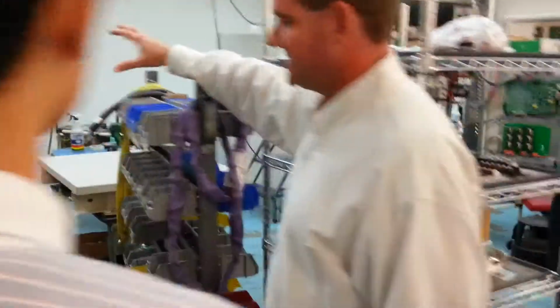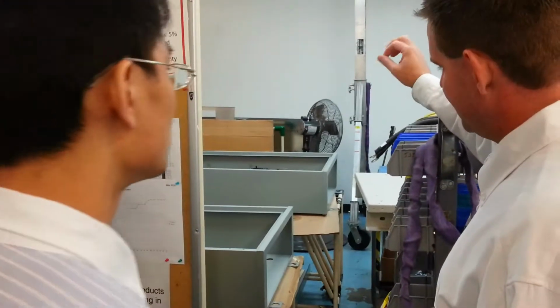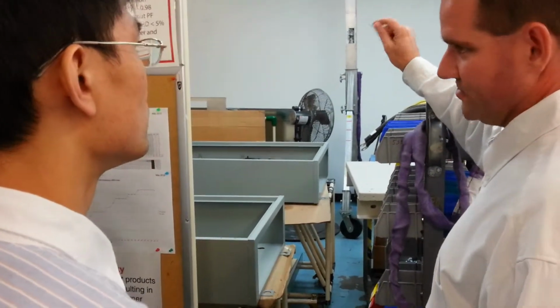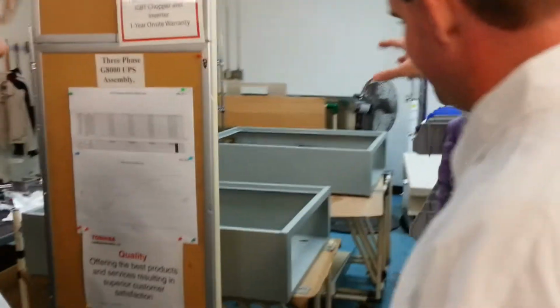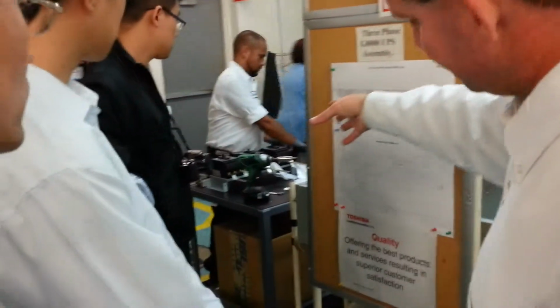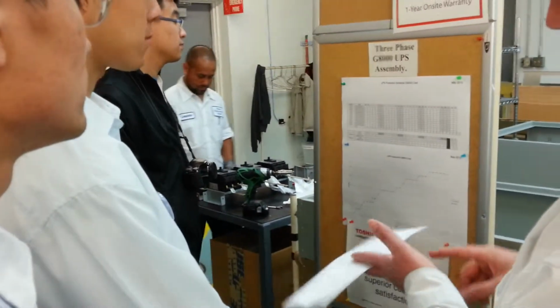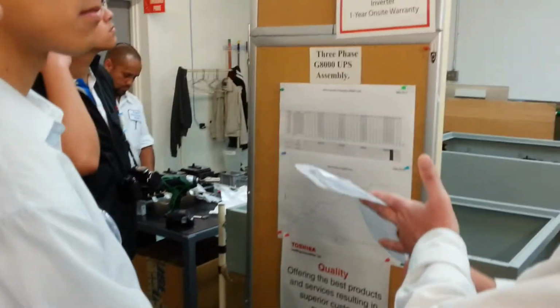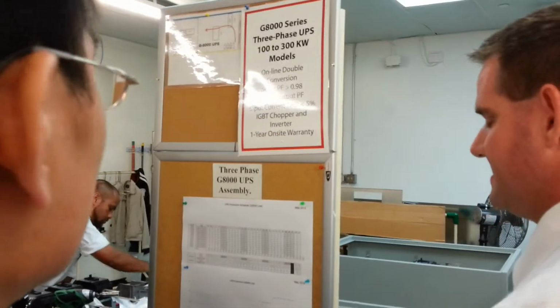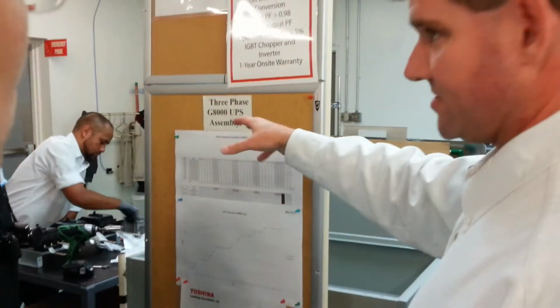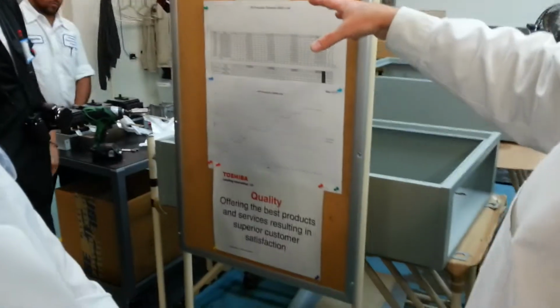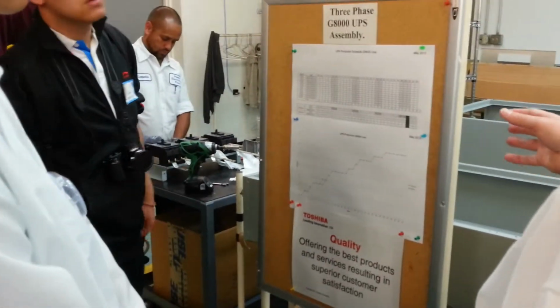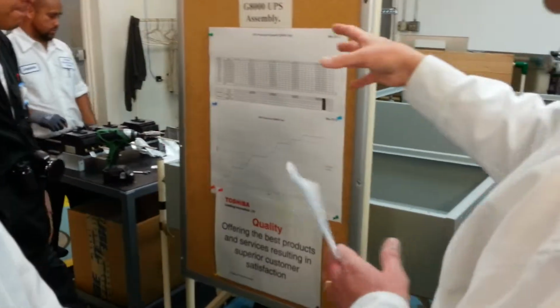We have these options, these are maintenance bypass cabinets. These are like big, large J boxes that the customer can buy, put in front of their unit. Instead of installing new electrical connections, new electrical boxes, they come in where they can actually select their input breakers and put in a maintenance bypass breakers. One for the input, one for the output. And if the customer or electrical person of the hospital, building, city official, he can actually come in, turn off, and put one of the breakers in maintenance bypass, turn on the breaker, wrap around the whole system, work on the unit, fix it, fire it back up, and then turn the breakers back on in a maintenance bypass operation.